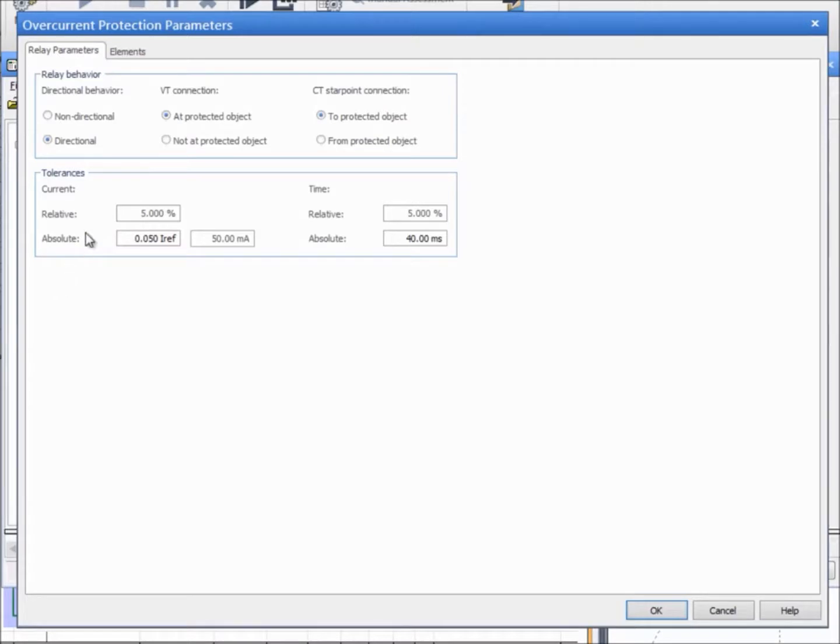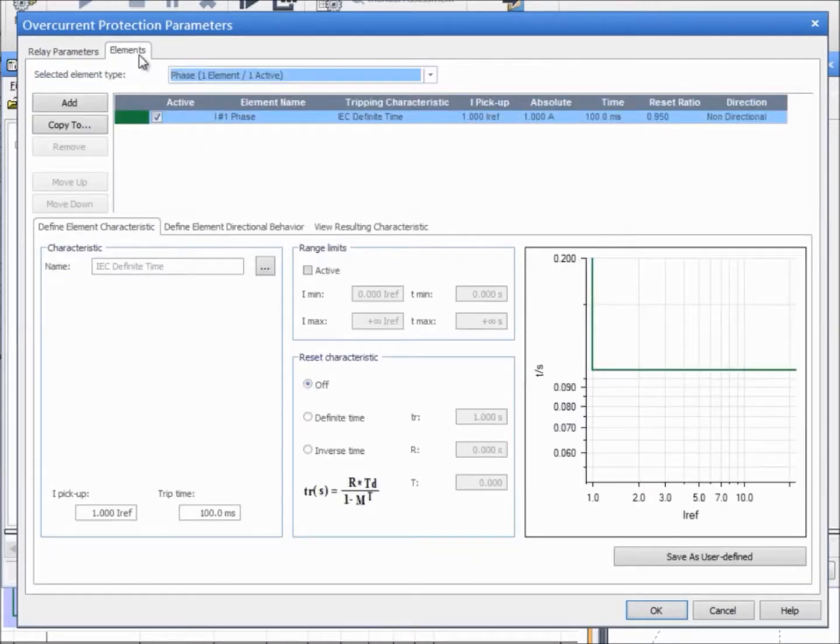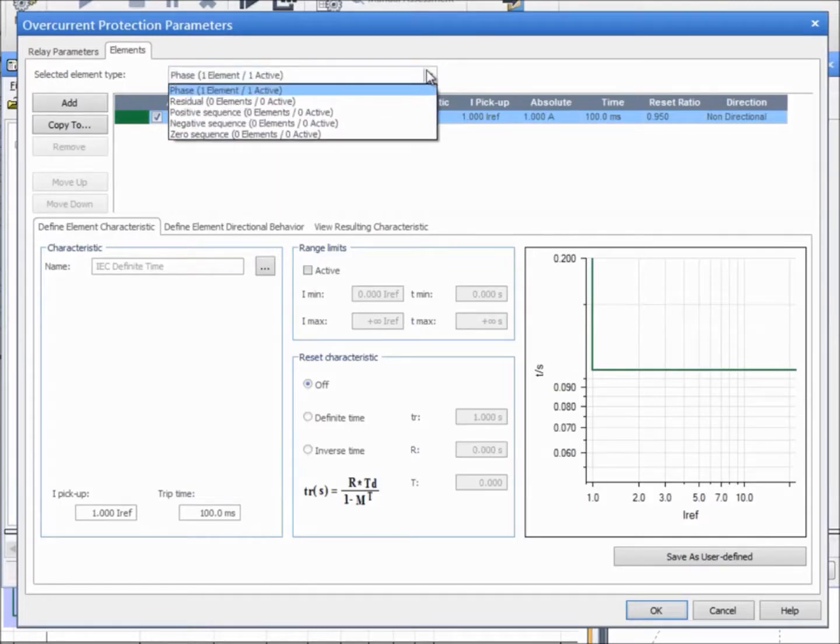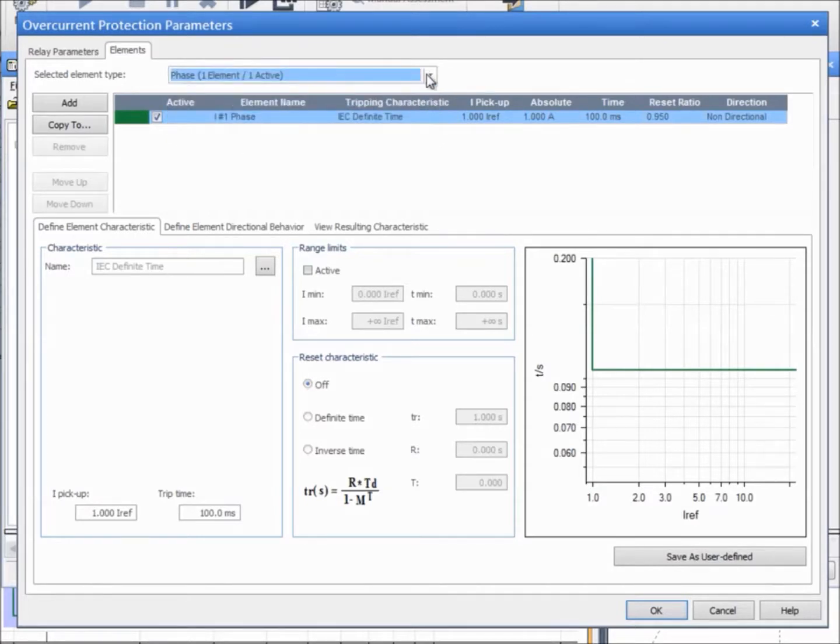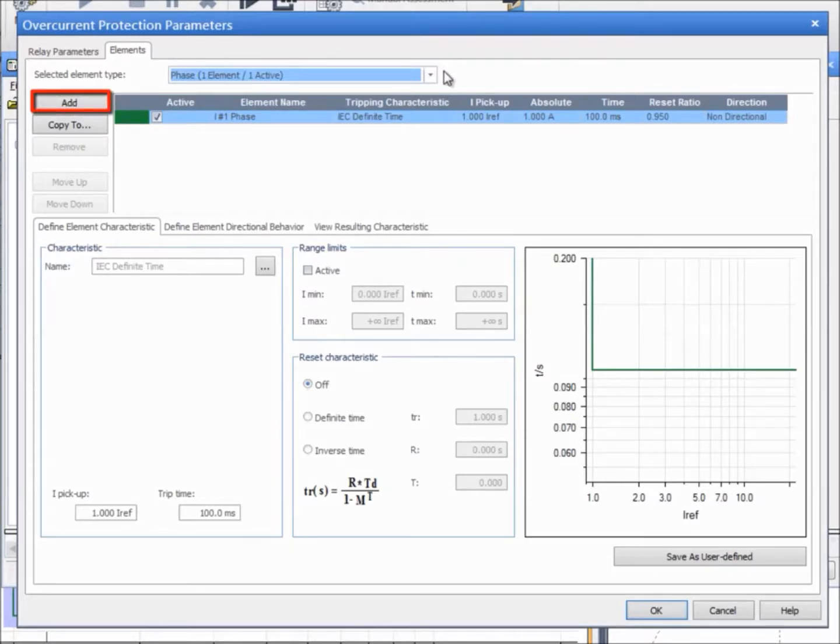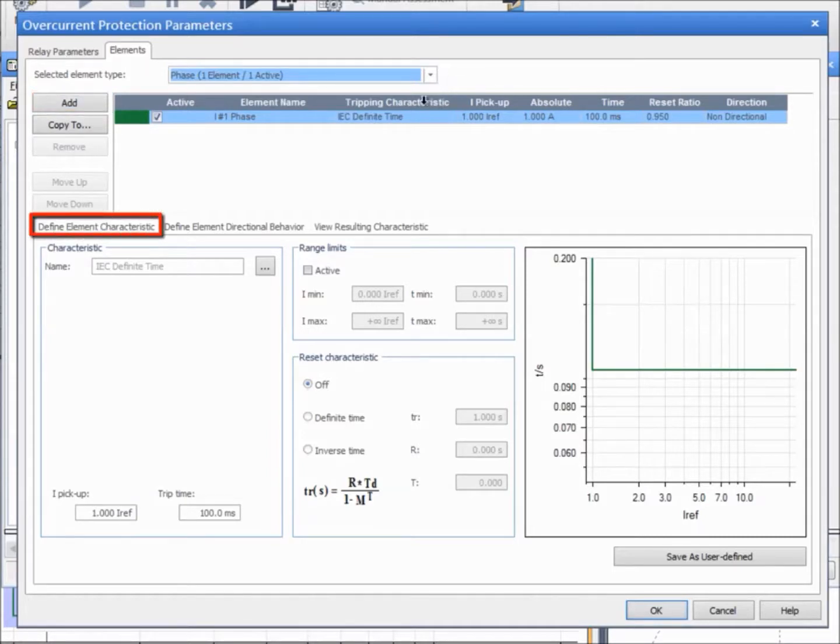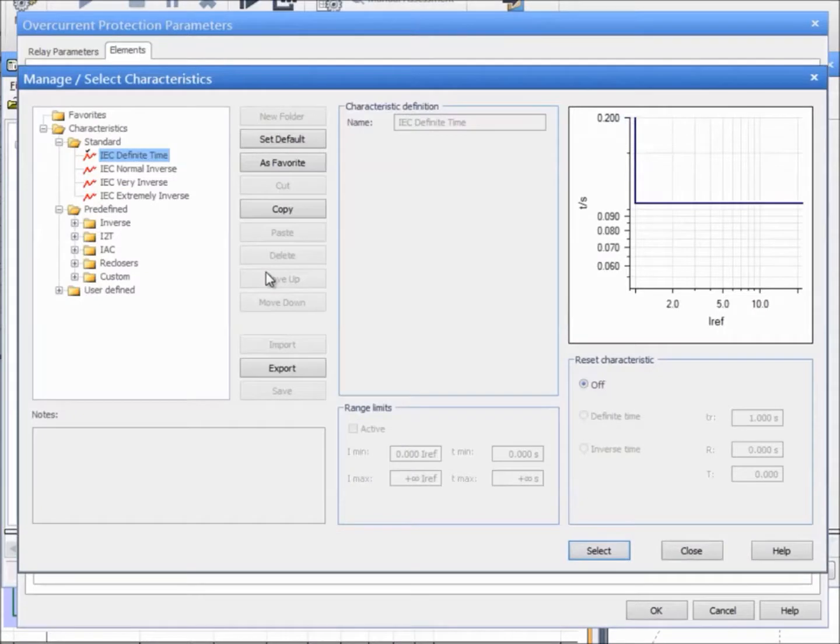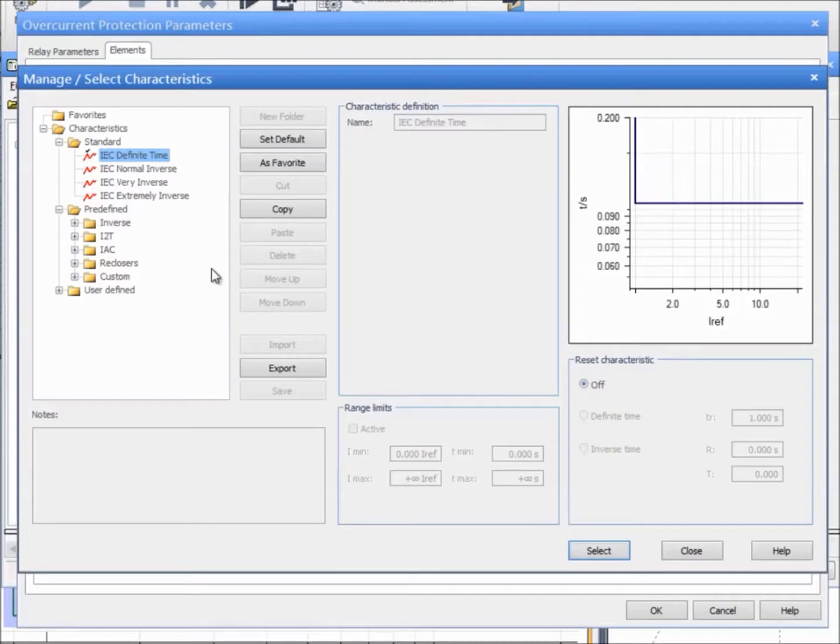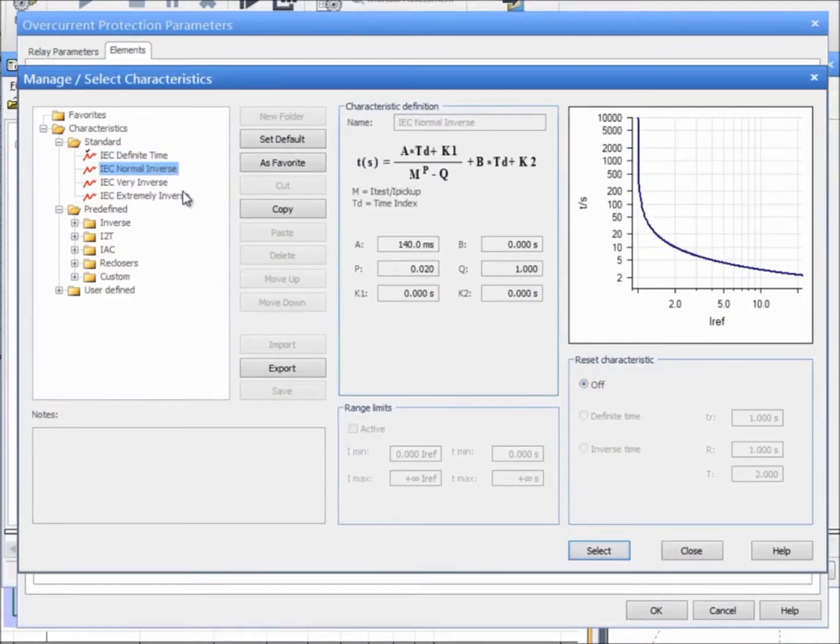The Elements tab is used to define the tripping elements of the relay. Test Universe supports different element types: phase, residual, positive sequence, negative sequence, or zero sequence. Each element type can integrate several tripping elements. Add the element type of your choice and configure the settings on the Define Element Characteristics tab. Click on the Browse button to get access to a list of standard predefined and user-defined characteristics. Among others, you can use Definite Time or Inverse Characteristics and adjust the parameters at your convenience.